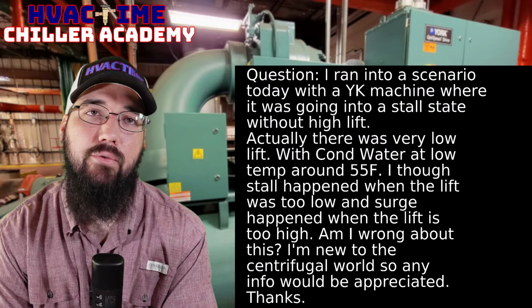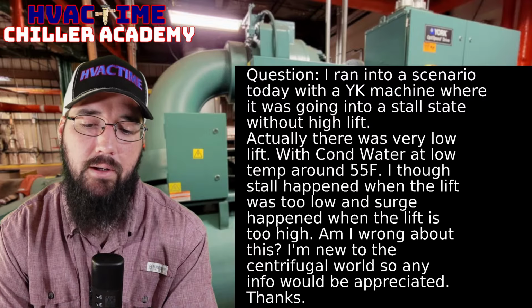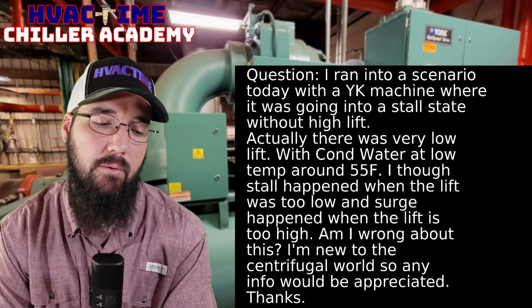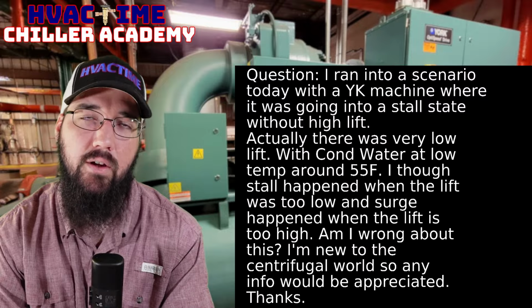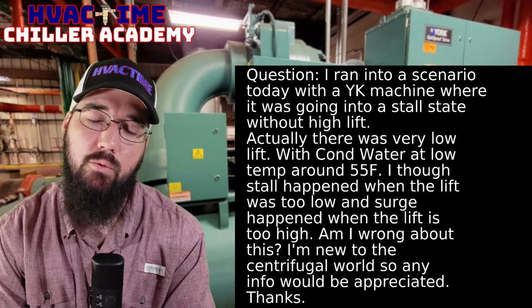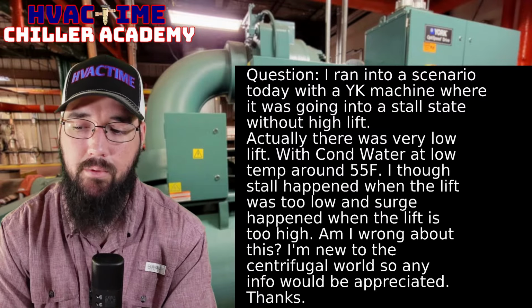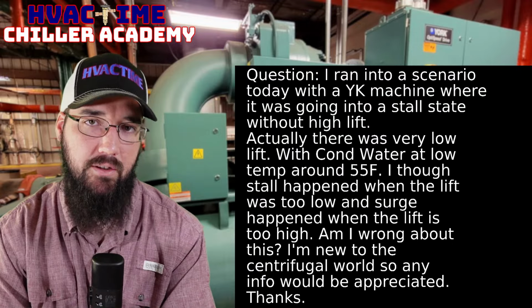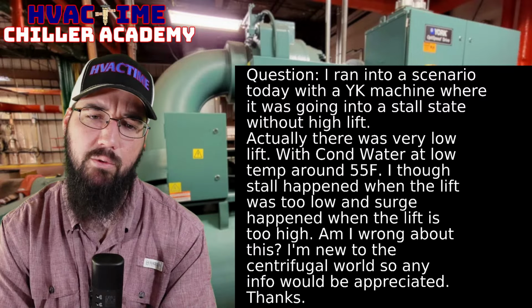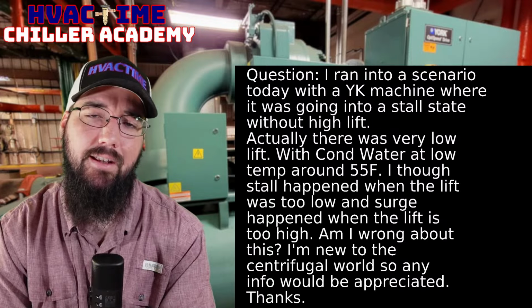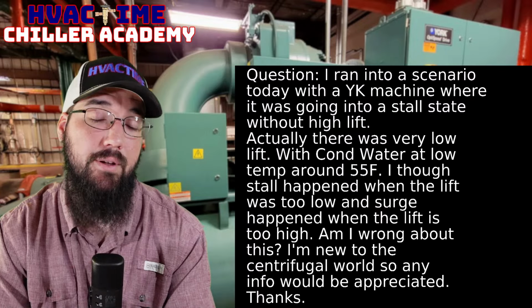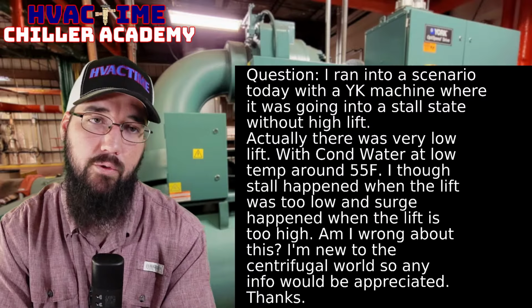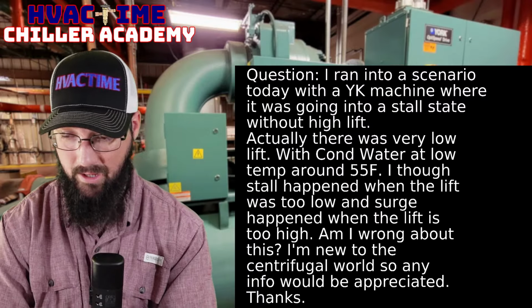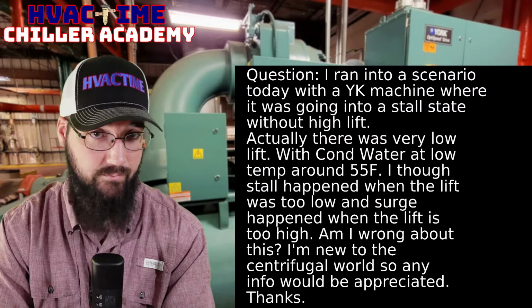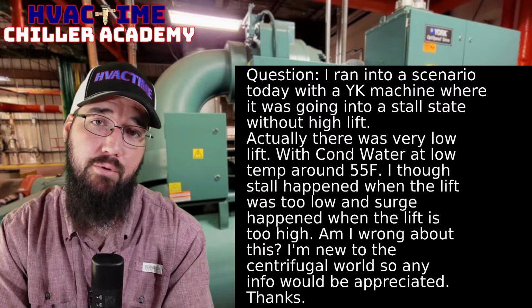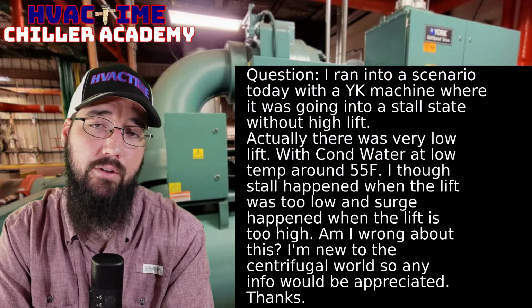But if you've listened to me talk about this, you'll also hear me talk about, as long as we have lots of load, right? So what do we qualify as load in this scenario? Well, it's our temperature differential across the evaporator. That's what we're paying attention to. So we really want to make sure that we have a high enough TD across the evap, which, if our GPM is correct, means that we've got plenty of load. So if we're talking a machine designed for 10 degrees and we're running at least 8 to 10, we've got lots of heat to put into the machine. The compressor can really open itself up, run wide open. It's going to run great.